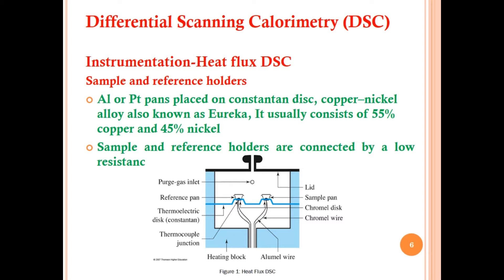The right side bottom shows a heating block, thermocouple junction, thermoelectric disc, constantan, reference pan, and purge gas inlet. We can use different types of purge gases in DSC — nitrogen, argon, carbon dioxide, and others. A thermocouple is a sensor that measures the temperature difference between two objects, meaning the reference and the sample.